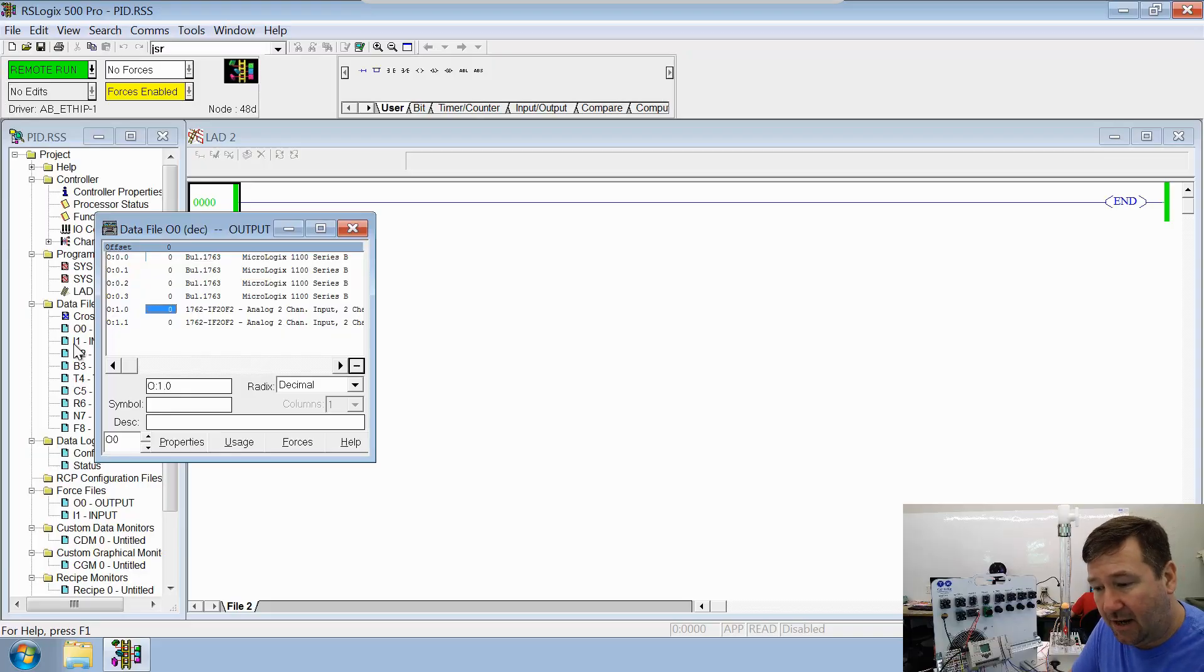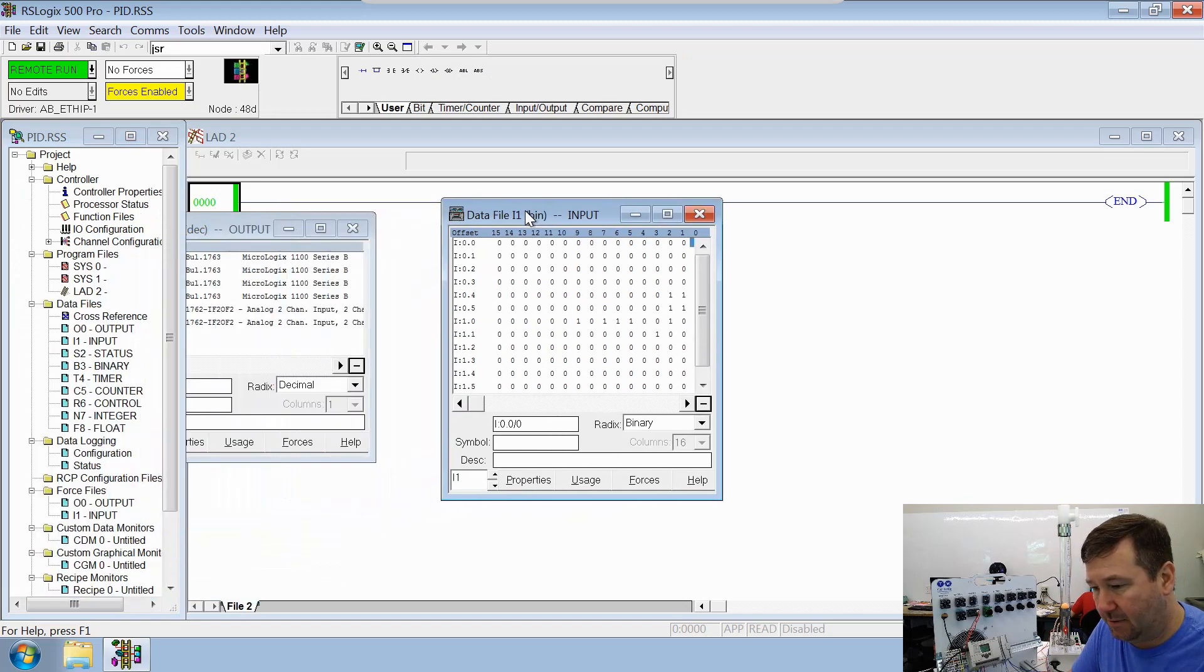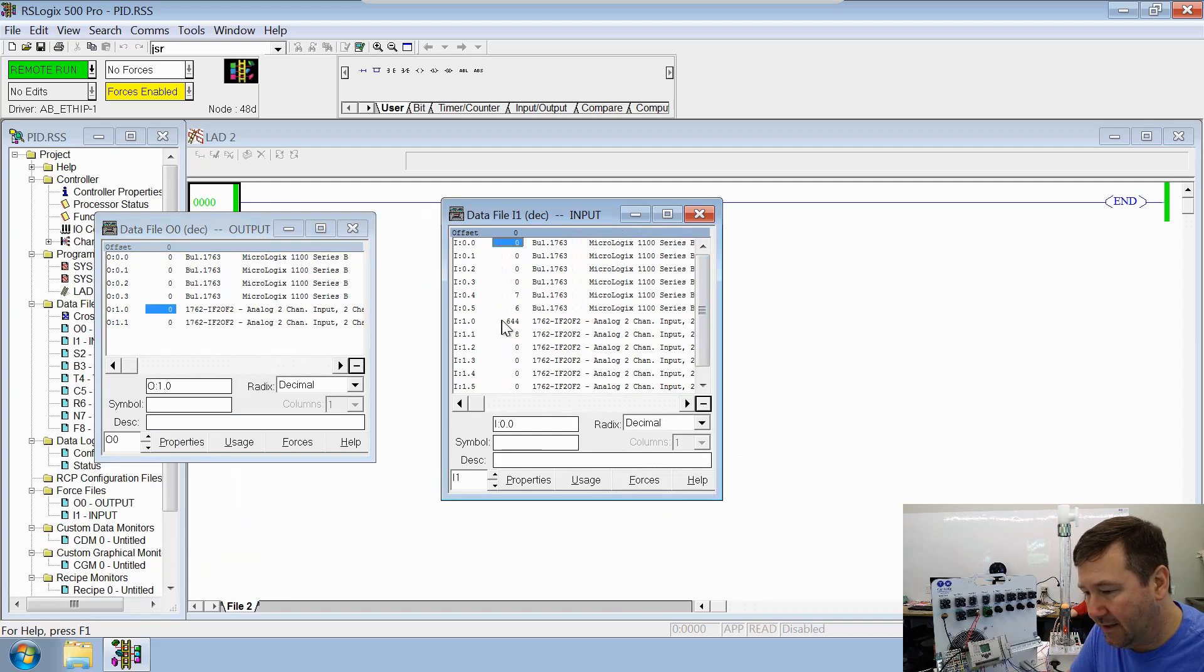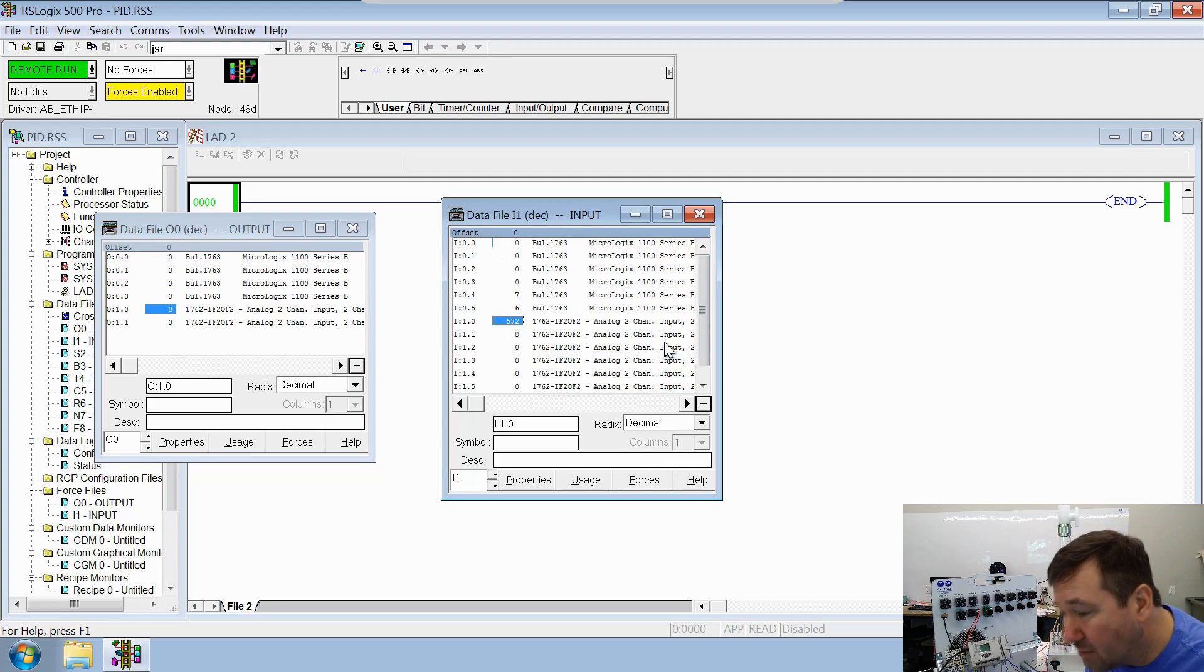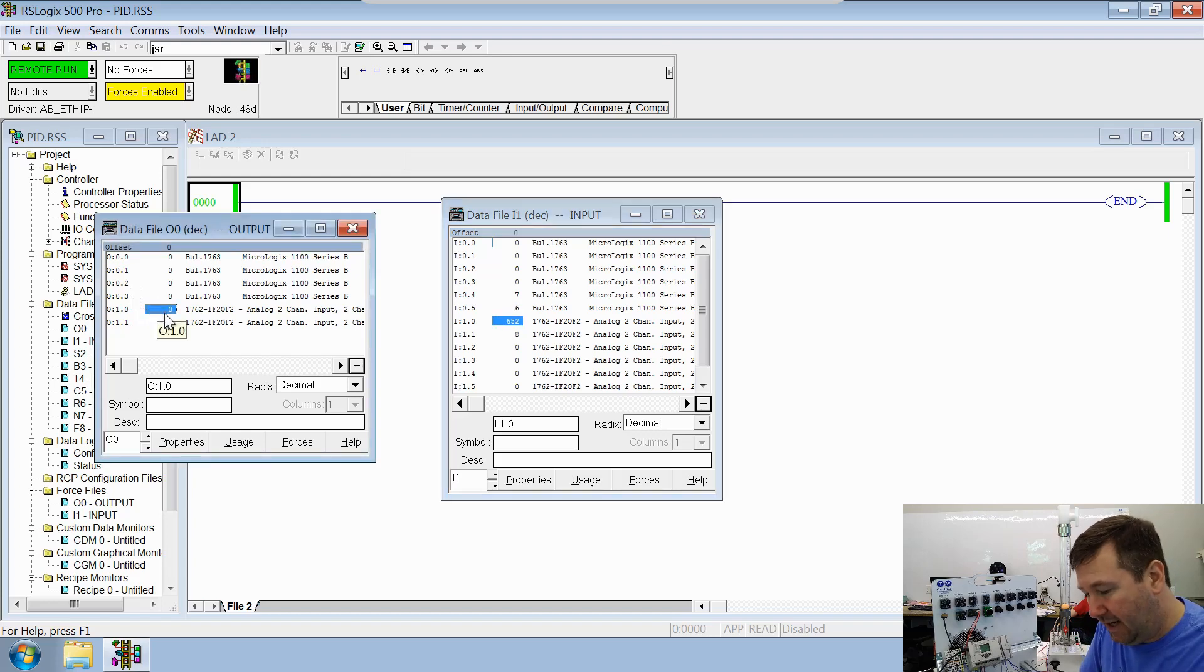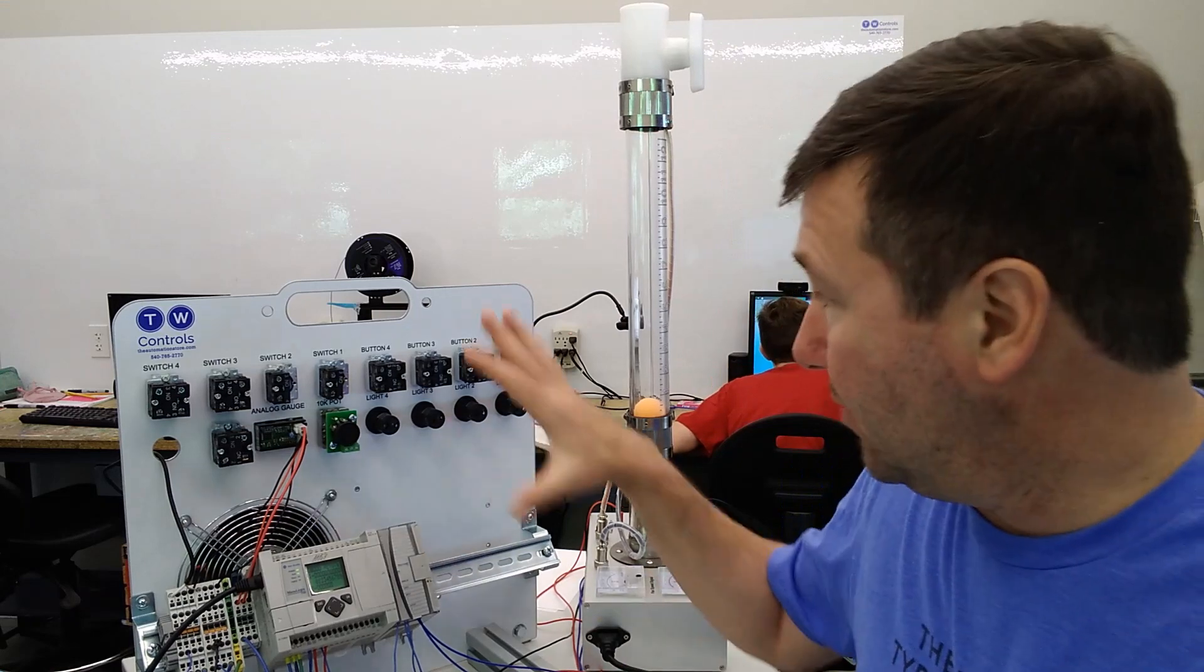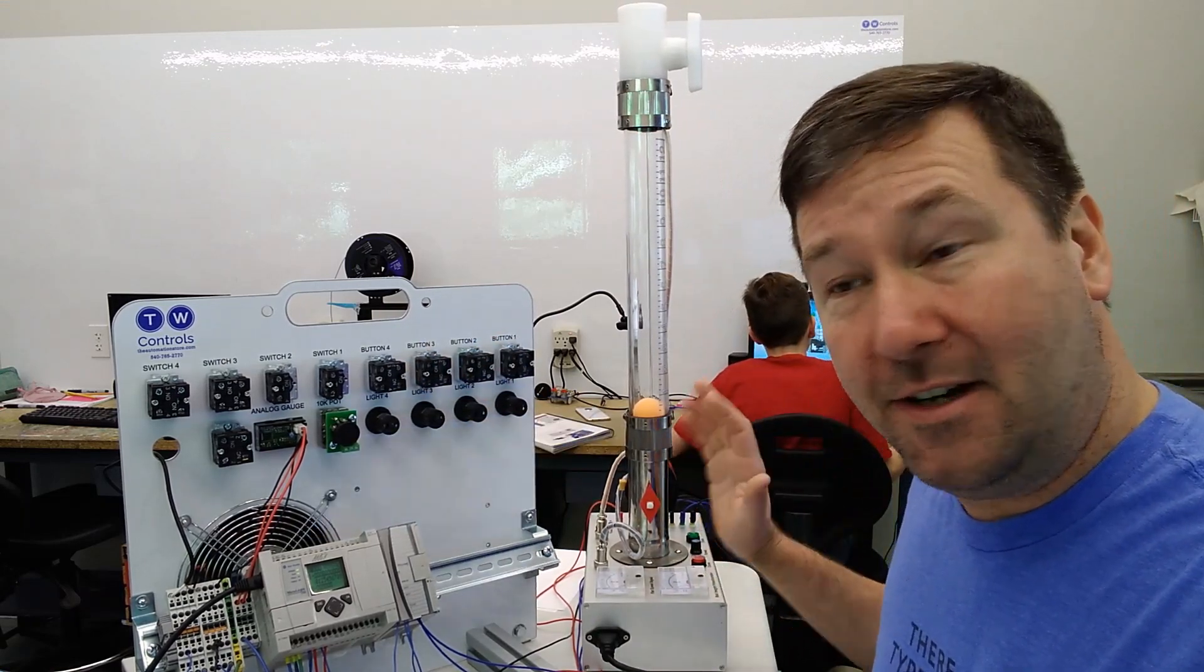Now let's check out our analog input. So let's open up our input data table. Let's drag them around where we can see both of them. And then we want to change our radix again to decimal. And there it is, input zeros. So when it's sitting still, it looks like somewhere around 600 is our bottom point. So then on our output, one zero, let's take that back up to around 30,000. All right, and we're around 12,000 on it. So all our IO interfaces are working between our PLC trainer and Industrial Concepts PID trainer.